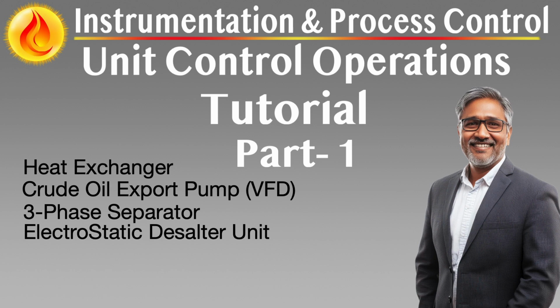Interface level control between oil and brine phases is increasingly handled by high-resolution guided wave radar, GWR, or dual interface capacitance probes. These sensors are more accurate than traditional displacers or DP transmitters, especially under foaming or emulsified conditions. Control loops maintain the oil-water interface within a safe and efficient separation zone, ensuring neither water upsets the downstream crude nor oil contaminates the brine.